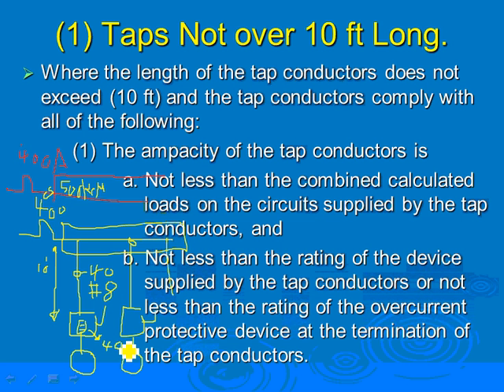That's why I always say, when everything is said and done, the enclosure to enclosure, because when you measure, you're not going to go to the terminals. Enclosure to enclosure, you're looking at 9 feet. Good point. To the enclosure of the disconnect. Now, how far can I go from this fuse all the way to this equipment? You guys are cool. No limit on that.